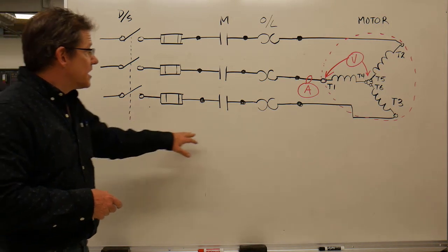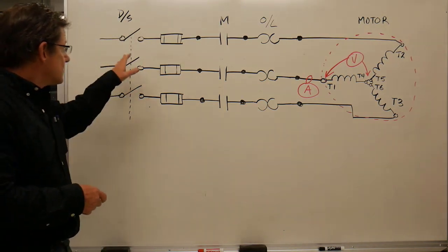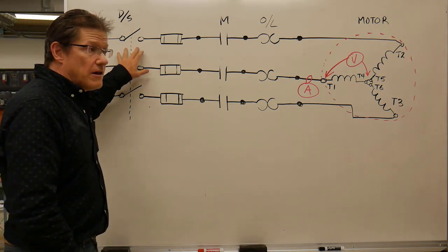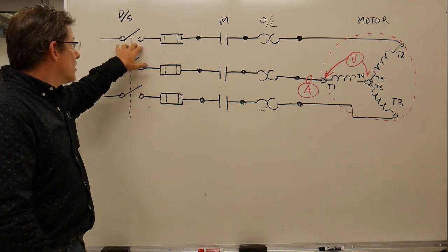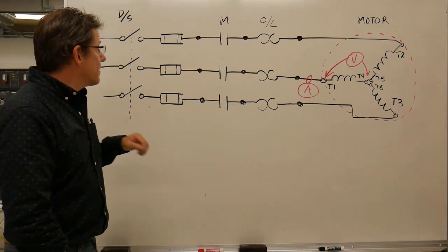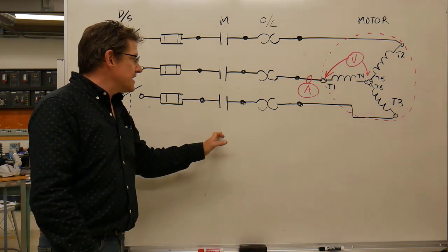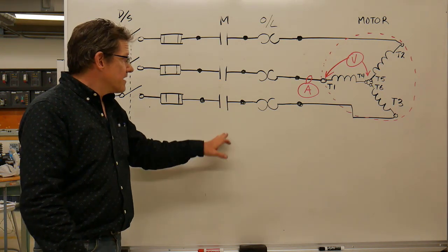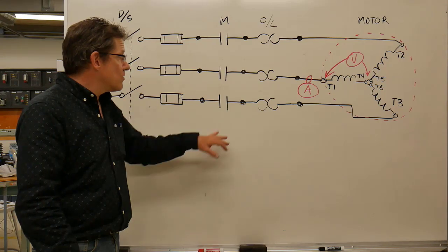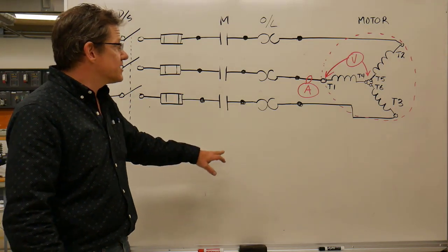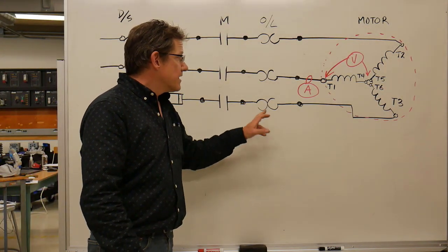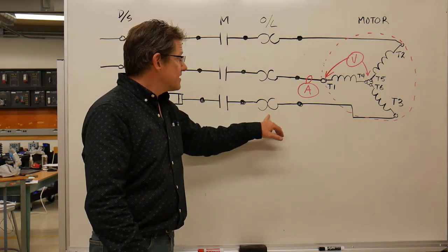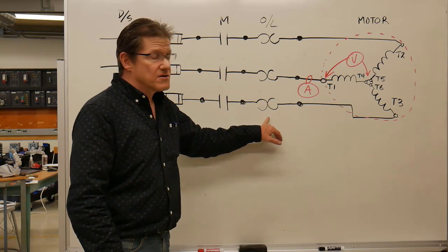We have our switches, our contacts, and our overloads. The linkage in these disconnects could fail, and when you close the disconnect switch, one of the blades may stay open. With our contactors, because they arc a little bit when they open and close, they eventually wear out and you can actually burn out one of the contacts. That can cause a single phase condition. The overload heaters can also burn open or overheat and develop an open. That'll also give us a single phase condition.